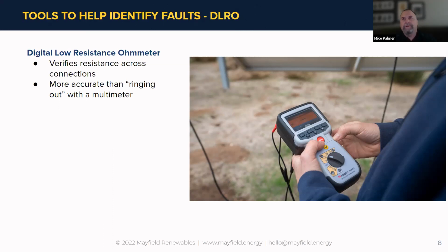And by the way, everybody's on the buzz feature of the continuity check, and nobody's looking at the reading on it. Raise your hand or send us a Q&A that you always look at the number on that continuity check. It won't surprise us if nobody says they know the number that's achieved with doing that continuity check. Low resistance measurements, on the other hand, is all about the reading, and it's all about testing that connection. So it'll show when degradation is occurring in these electrical elements.